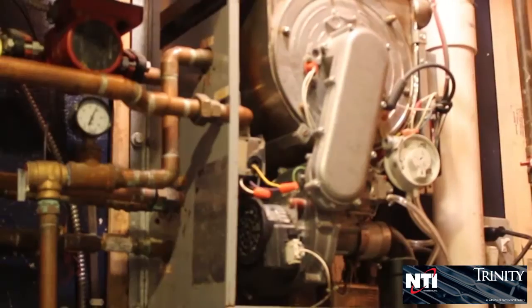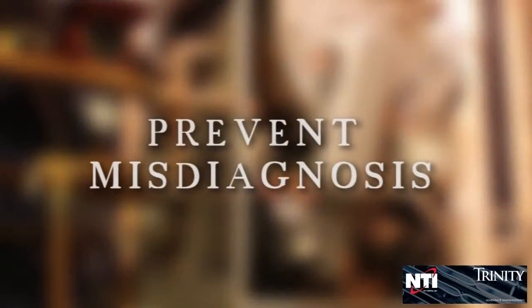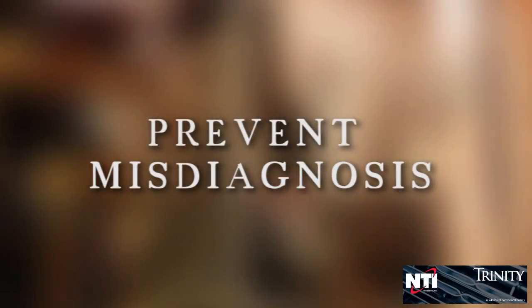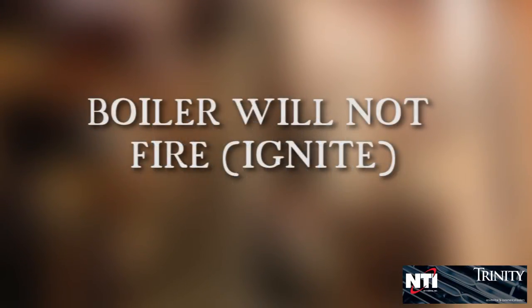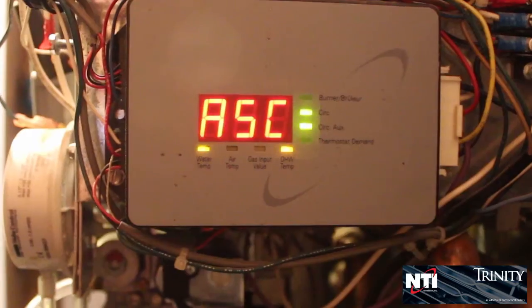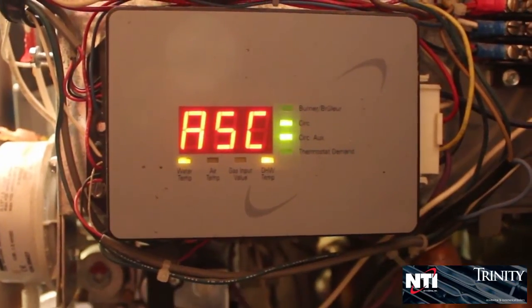Hey, this is Harry again from Climatech Service with another helpful tip on your Trinity TI boiler. This video can help you prevent misdiagnosing a common problem on your boiler. The first thing you'll notice is that the boiler won't fire. The display on the Sentry controller will indicate an ASC code.